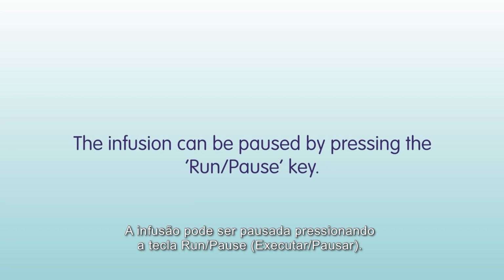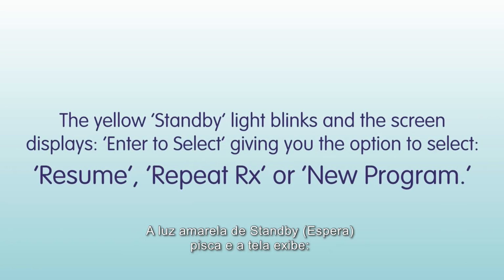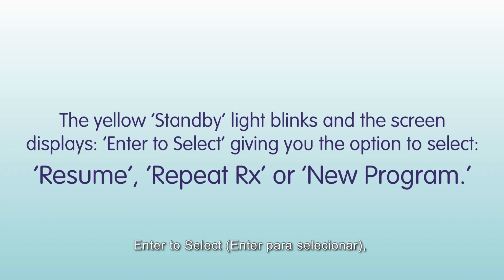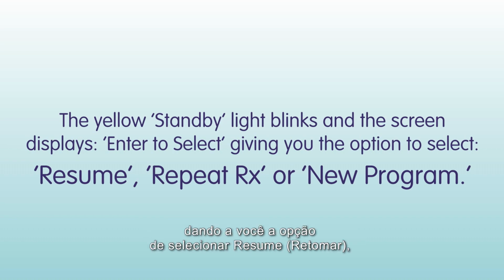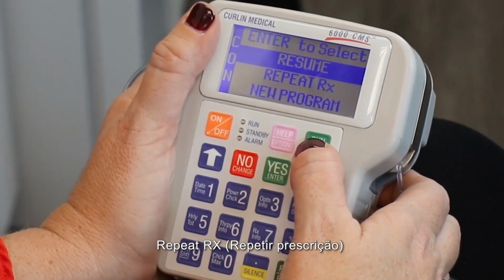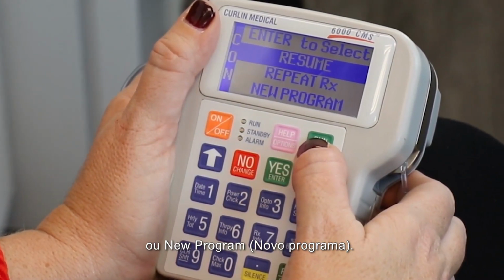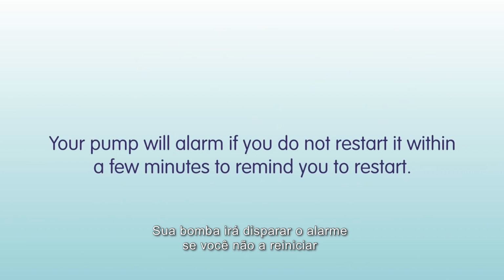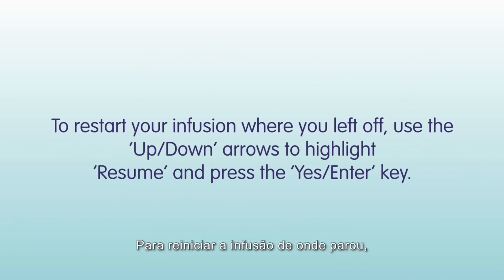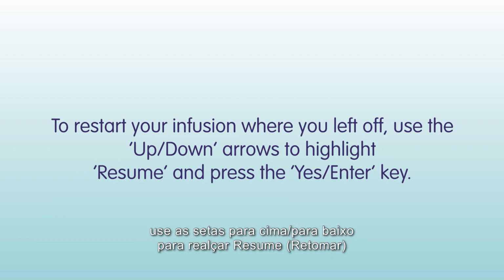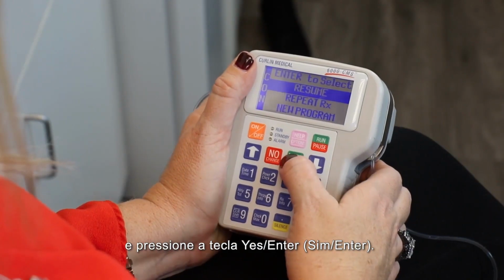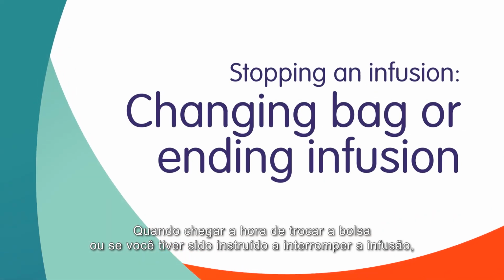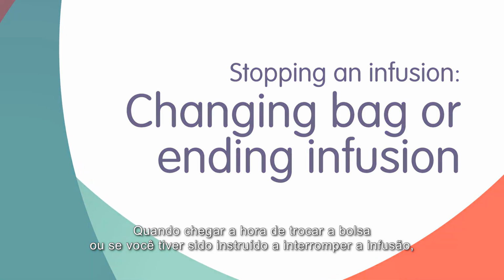The infusion can be paused by pressing the Run Pause key. The yellow standby light blinks and the screen displays Enter to select, giving you the option to select Resume, Repeat RX, or New Program. Your pump will alarm if you do not restart it within a few minutes. To restart your infusion where you left off, use the up-down arrows to highlight Resume and press the Yes Enter key.